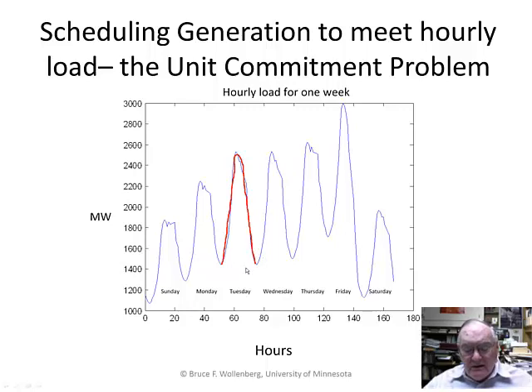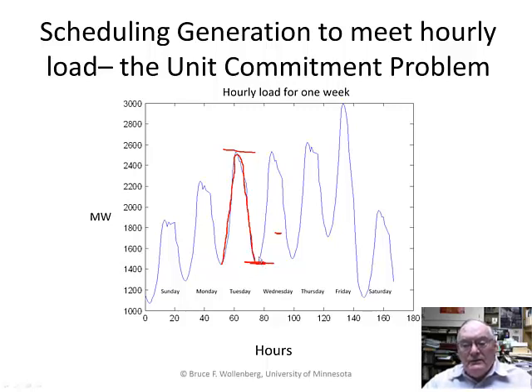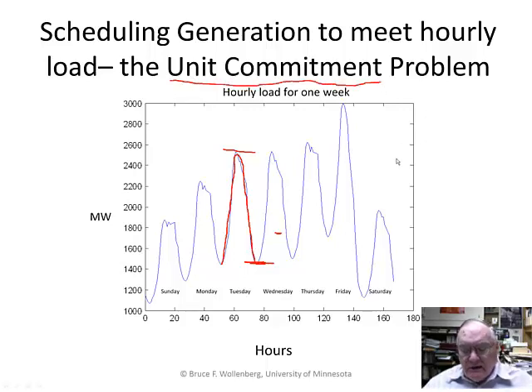We need to provide enough generation to meet that peak. But because the load is going up and down, we need a lot of generators at peak and we need to take some generators offline when load is low; otherwise they don't operate efficiently. So for the sake of economics, we put generators on, take them off, and put them back on. That process is called unit commitment — it simply means putting generators on and offline.